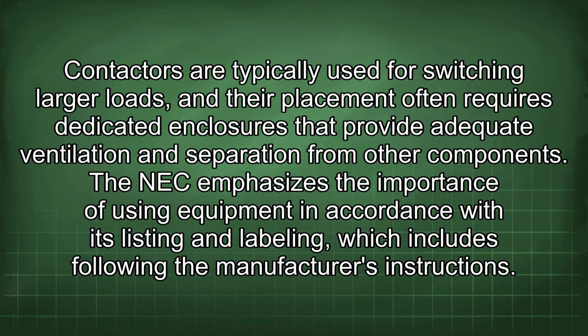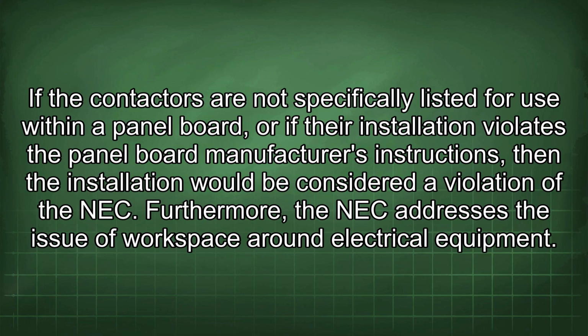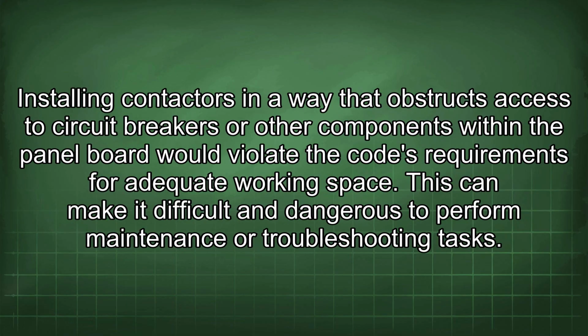The NEC emphasizes the importance of using equipment in accordance with its listing and labeling, which includes following the manufacturer's instructions. If the contactors are not specifically listed for use within a panel board, or if their installation violates the panel board manufacturer's instructions, then the installation would be considered a violation of the NEC. Furthermore, the NEC addresses the issue of workspace around electrical equipment. Installing contactors in a way that obstructs access to circuit breakers or other components within the panel board would violate the code's requirements for adequate working space. This can make it difficult and dangerous to perform maintenance or troubleshooting tasks.